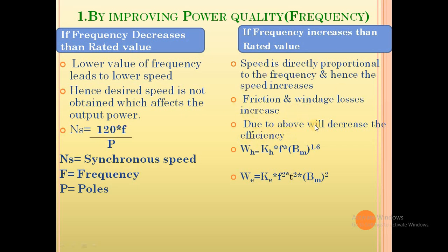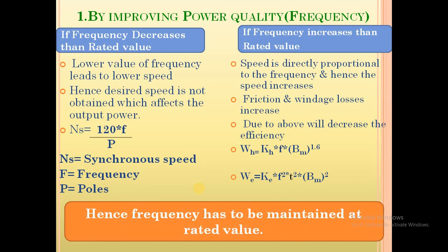So due to the above reasons, the efficiency of the induction motor may decrease, and also if frequency increases, hysteresis loss also increases because frequency is in the equation. If frequency increases, hysteresis loss increases. If frequency increases, eddy current loss increases. So if there is a decrease in frequency, we have a loss. If there is an increase in frequency, there is also loss. Hence, it is very necessary to maintain the frequency at the rated value of the induction motor.